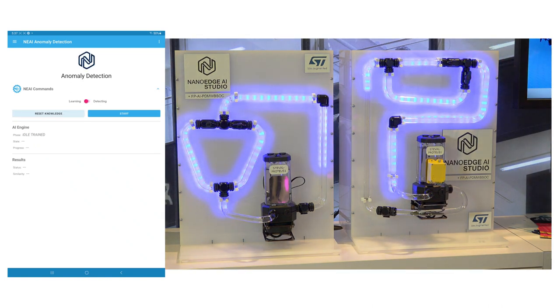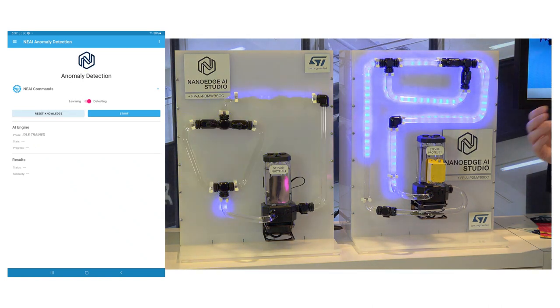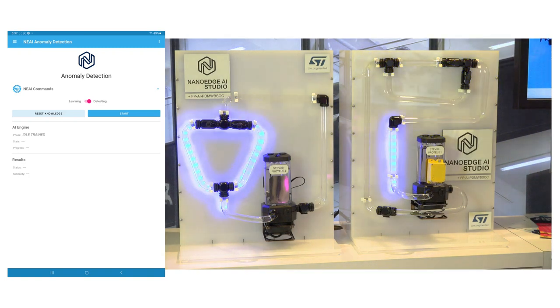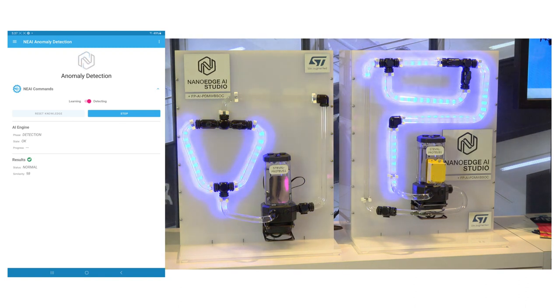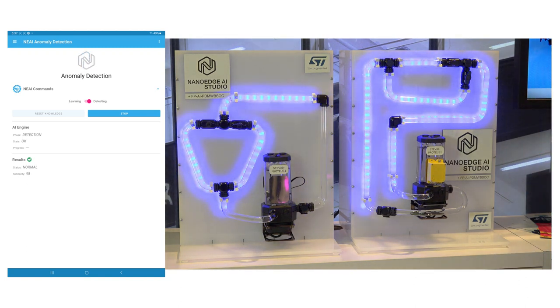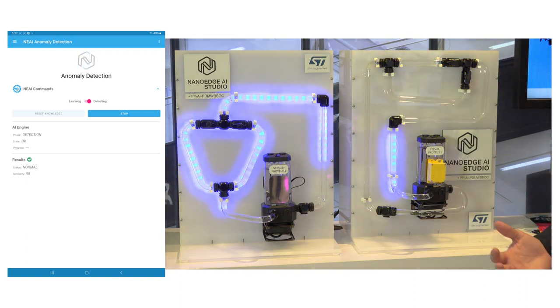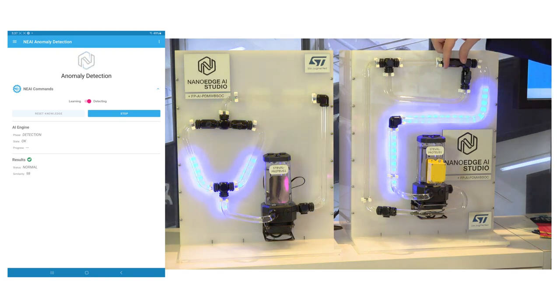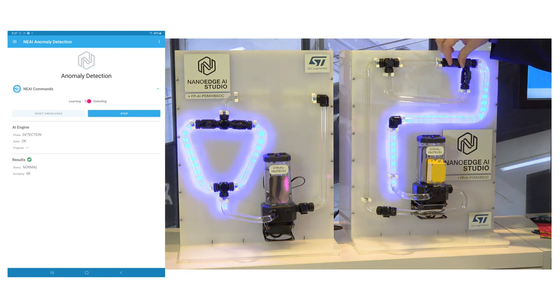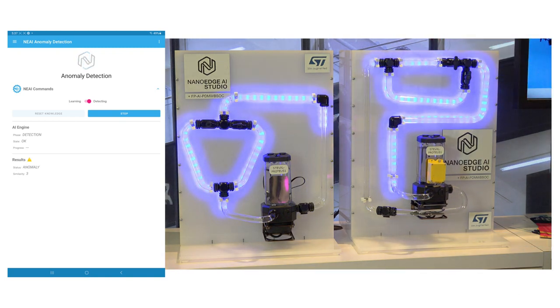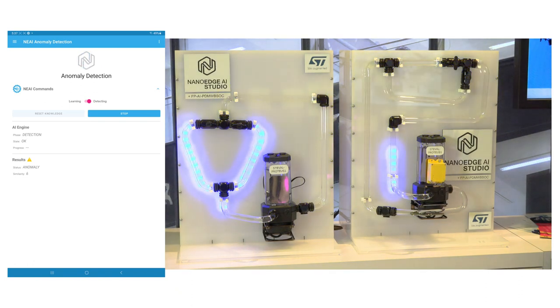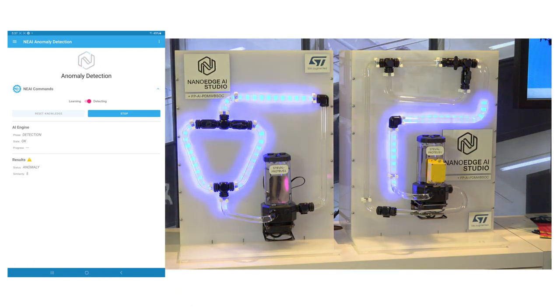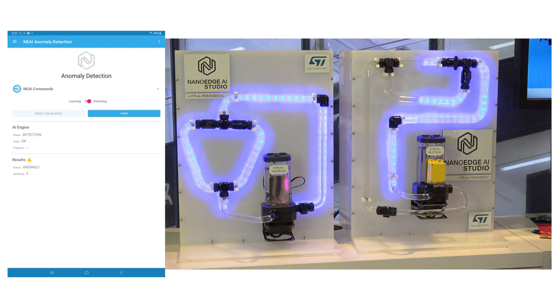Now that the learning is over, we can see that the status is normal and the similarity is very high — meaning it's very similar to what it has learned. If I shut off one of the valves of the water circuit, we can see the status goes to anomaly and the similarity score goes very low, as it's very different from what we've learned.